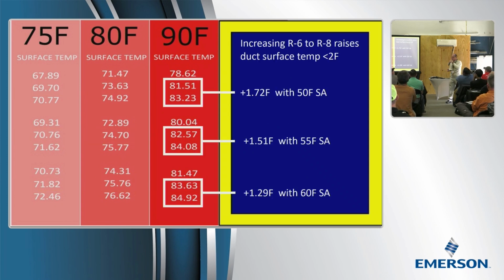Okay, so the next question is, what if I use R6 instead of R8? One of the things that we've proven to ourselves in our climate zone for years is there is no energy payback for R8 ductwork. And I'm on one of the building code committees where our values are over-discussed, in my opinion. But anyway, the R8 duct board, if you've ever used it, add 4 inches to your duct dimension. So if it's a 10 by 10 duct, it's going to be 18 by 18. Or excuse me, a 10-inch duct is going to be plus 14 by 14.